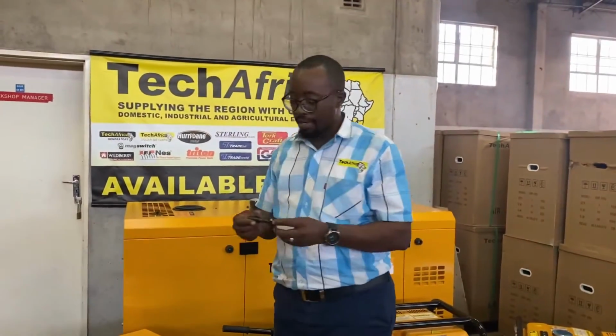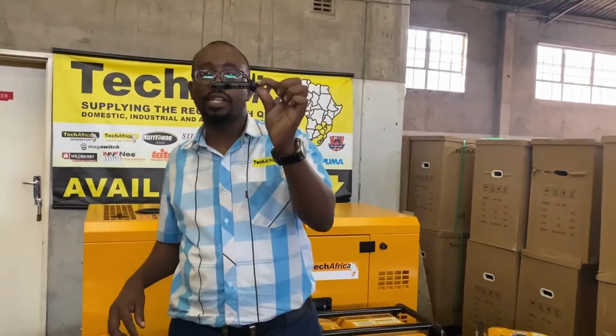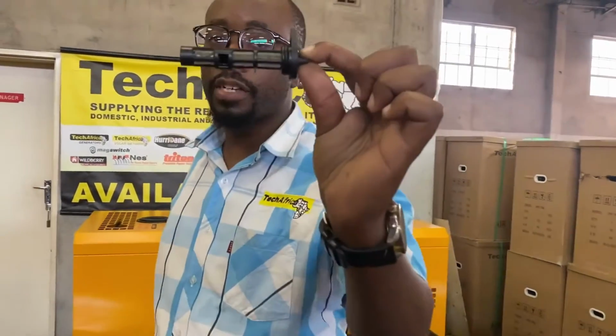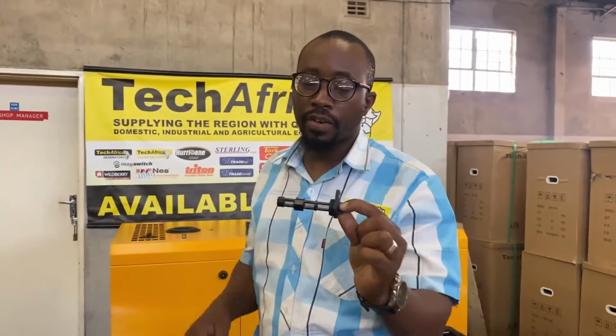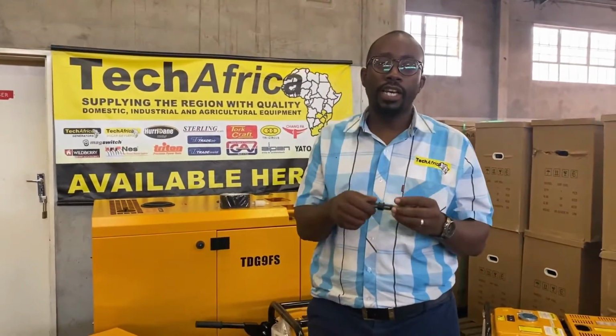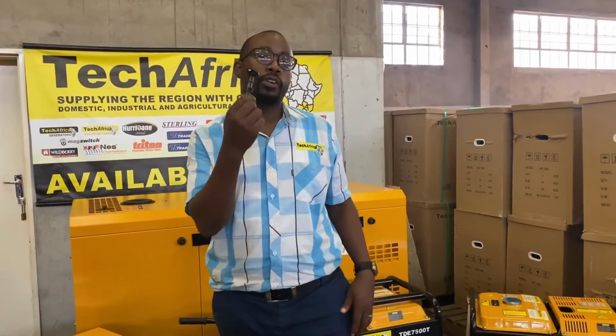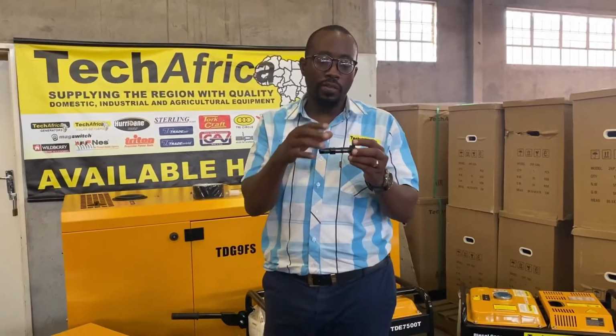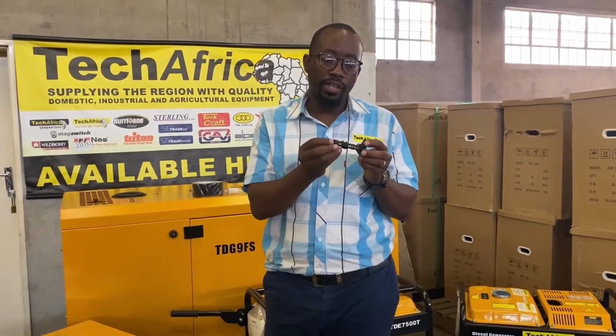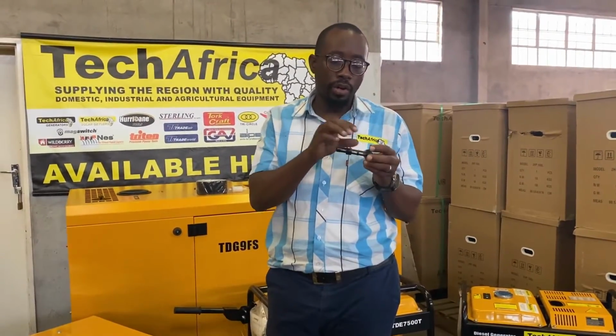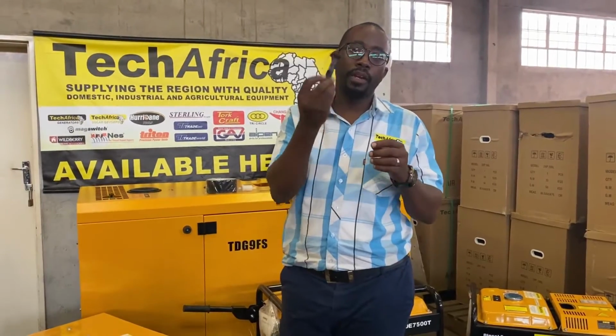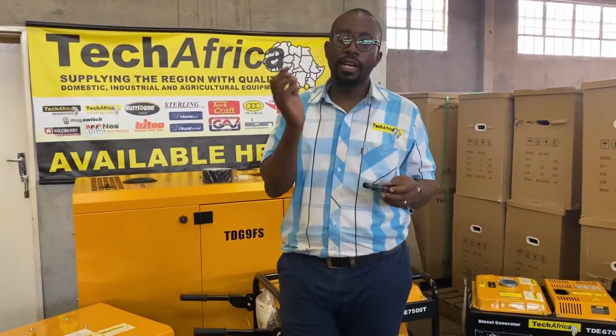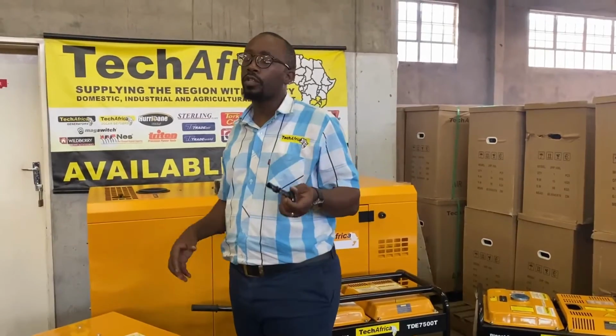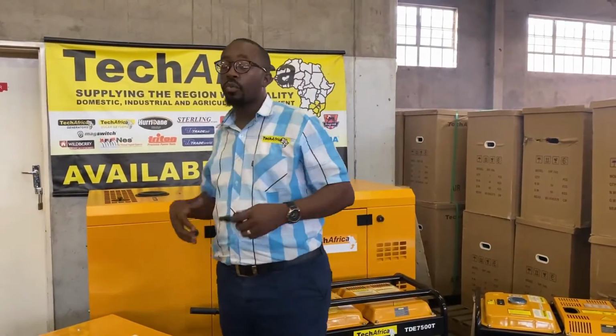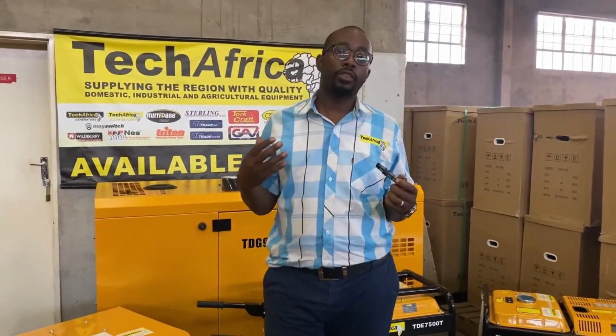Ladies and gentlemen, this is what you call the oil filter for the generator. You need to change the oil and the oil filter at 20 hours so that all the filings trapped within the oil filter remain on the filter, then drain the oil and replace with a new filter and new oil. That's basically what you do at 20 hours.